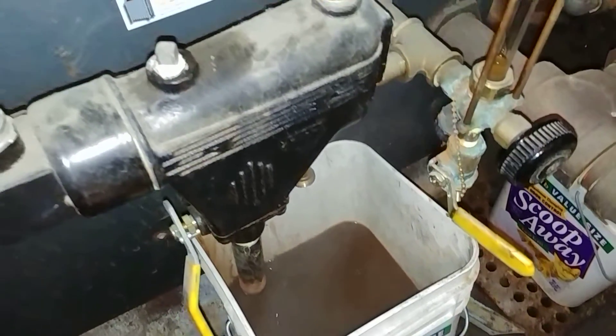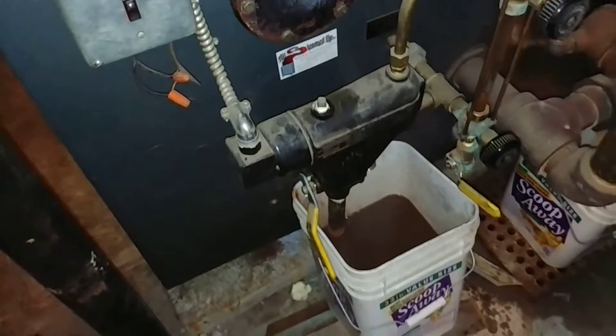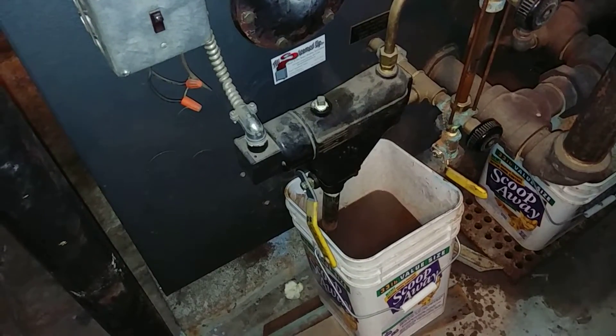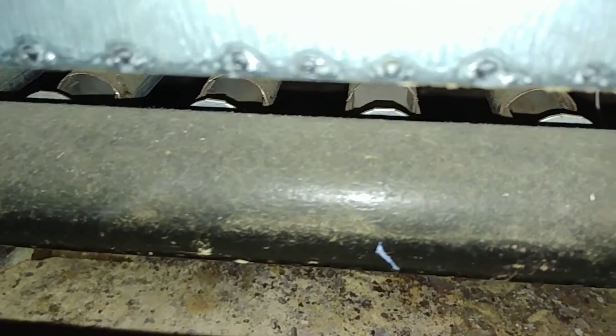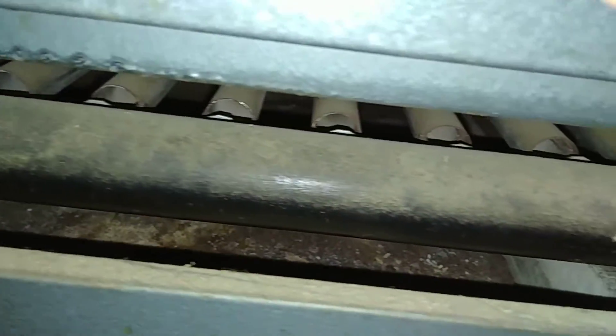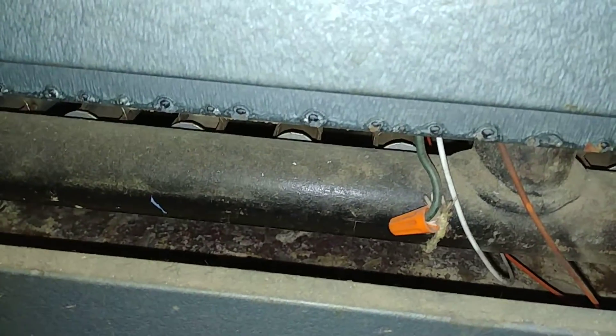There's an awful lot of stuff in there. For a second there was a little burning in the tubes — that's something that generally happens when you down-fire a boiler. Sometimes you don't get a good ignition; one of the tubes will occasionally burn down in there.